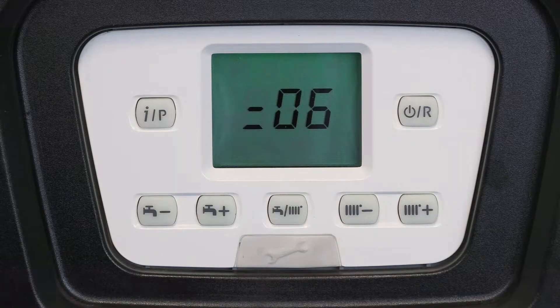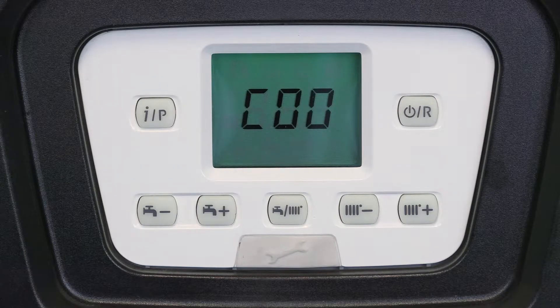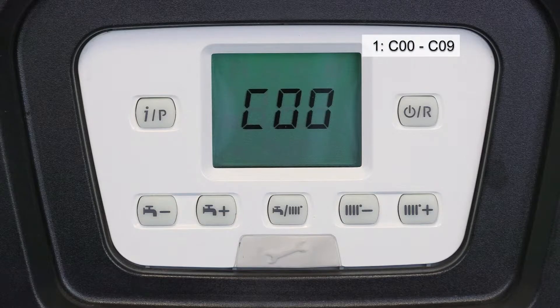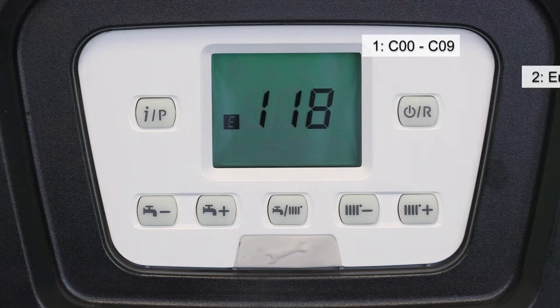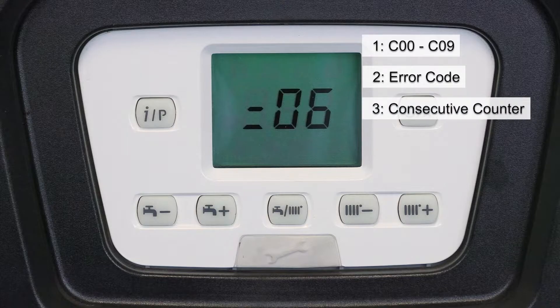Once there, three different numbers will flash on the screen. The first one will be C00 — this is the error storage number in order from C00 to C09. The second number flashing is the actual error code. The third number is the consecutive error code counter of the same error, telling you how many times consecutively this error has occurred.